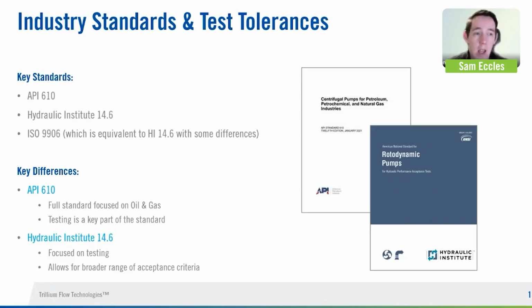Key differences here, API 610 is, for those who aren't familiar, American Petroleum Institute. So as you can understand, it's very focused on oil and gas. It is not a testing standard. It is a complete standard for manufacturing centrifugal pumps. This is good and bad. This means it's much more prescriptive, which for 80-90% of applications is a very good thing. It's straightforward, it's clear, the guidance is in place.